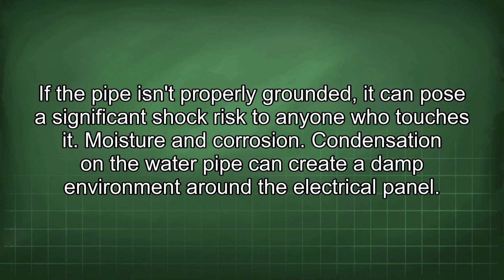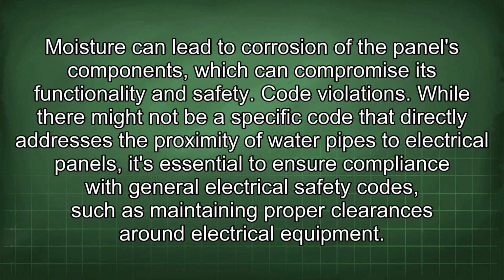Moisture and corrosion. Condensation on the water pipe can create a damp environment around the electrical panel. Moisture can lead to corrosion of the panel's components, which can compromise its functionality and safety. Code violations. While there might not be a specific code that directly addresses the proximity of water pipes to electrical panels, it's essential to ensure compliance with general electrical safety codes, such as maintaining proper clearances around electrical equipment.